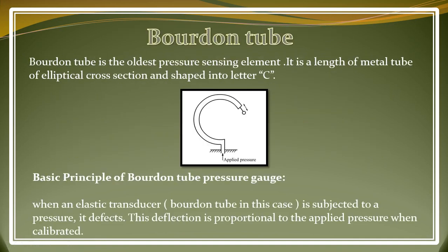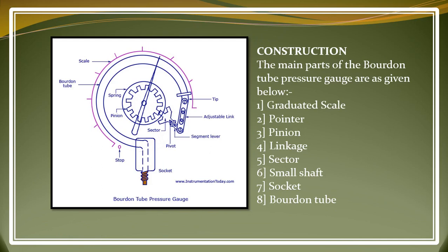First one is the Bourdon tube. What is the Bourdon tube? The Bourdon tube is the oldest pressure sensing element. In a Bourdon tube there is a length of metal tube of elliptical cross section shaped into the letter C. As you can understand, it is a metallic tube shaped like the English letter C, and its cross section is elliptical. How does it work? The basic principle behind the Bourdon tube: when an elastic transducer like a Bourdon tube is subjected to a pressure, it deflects. This deflection is proportional to the applied pressure when calibrated. This is the principle.